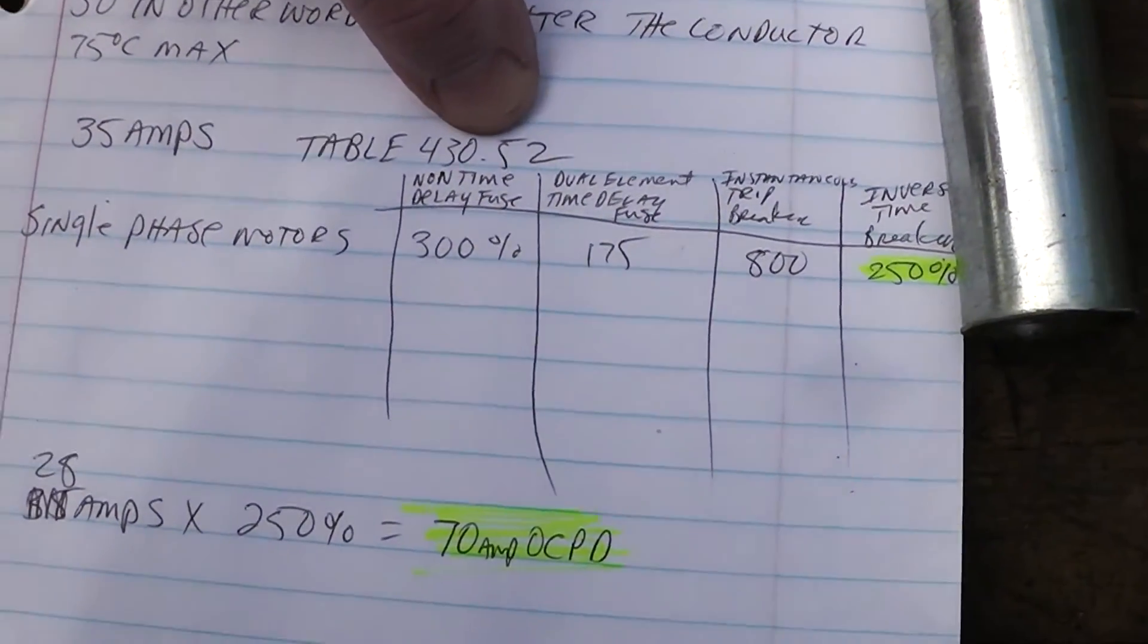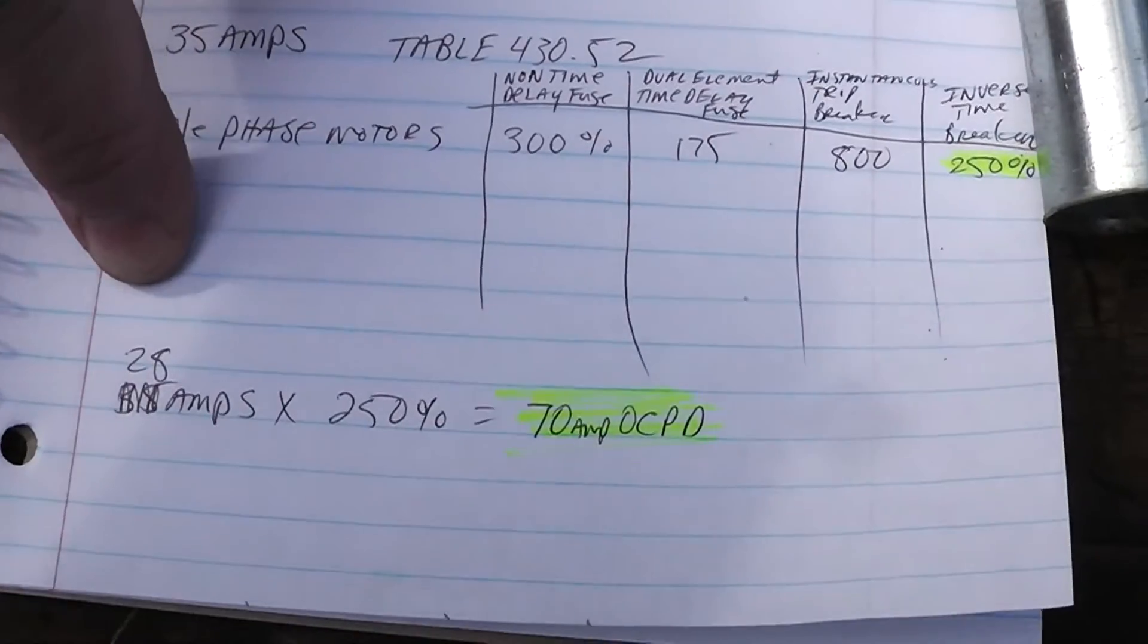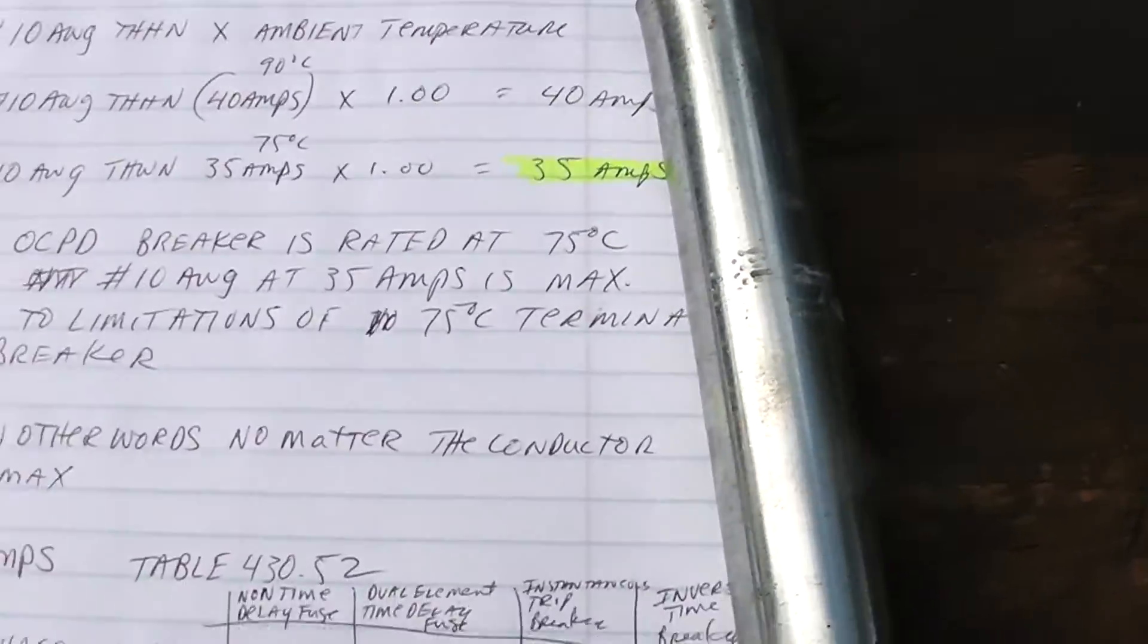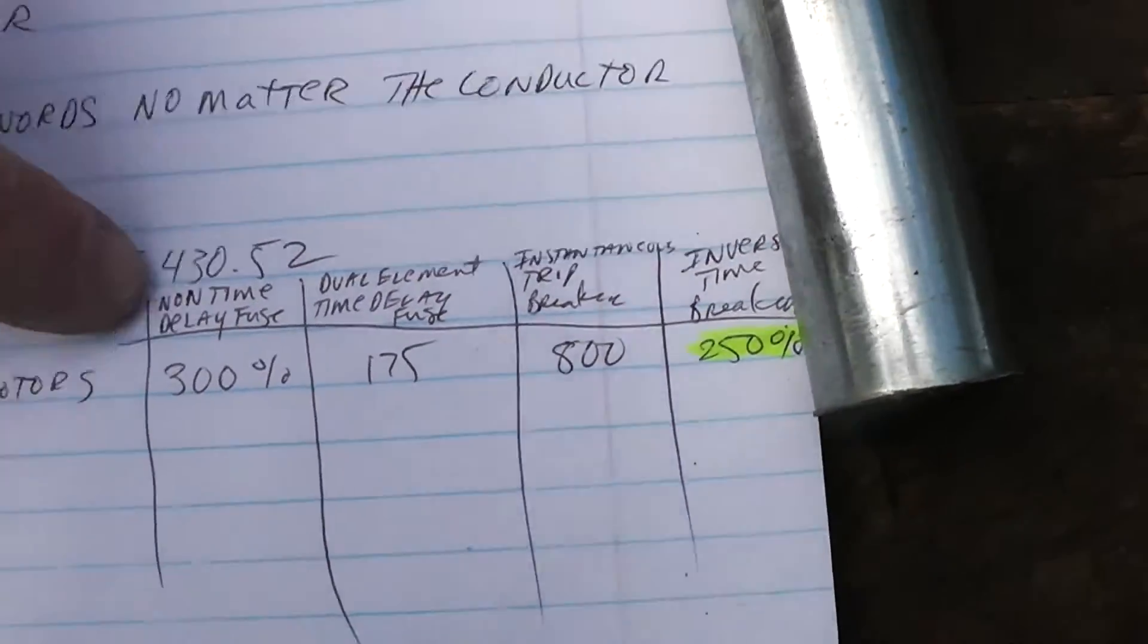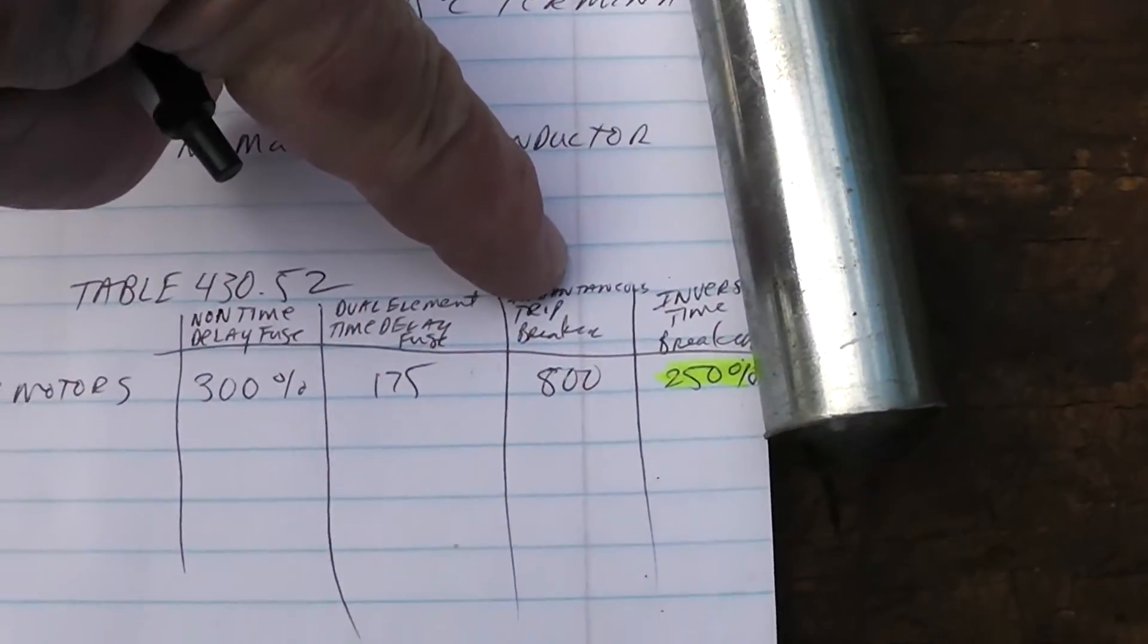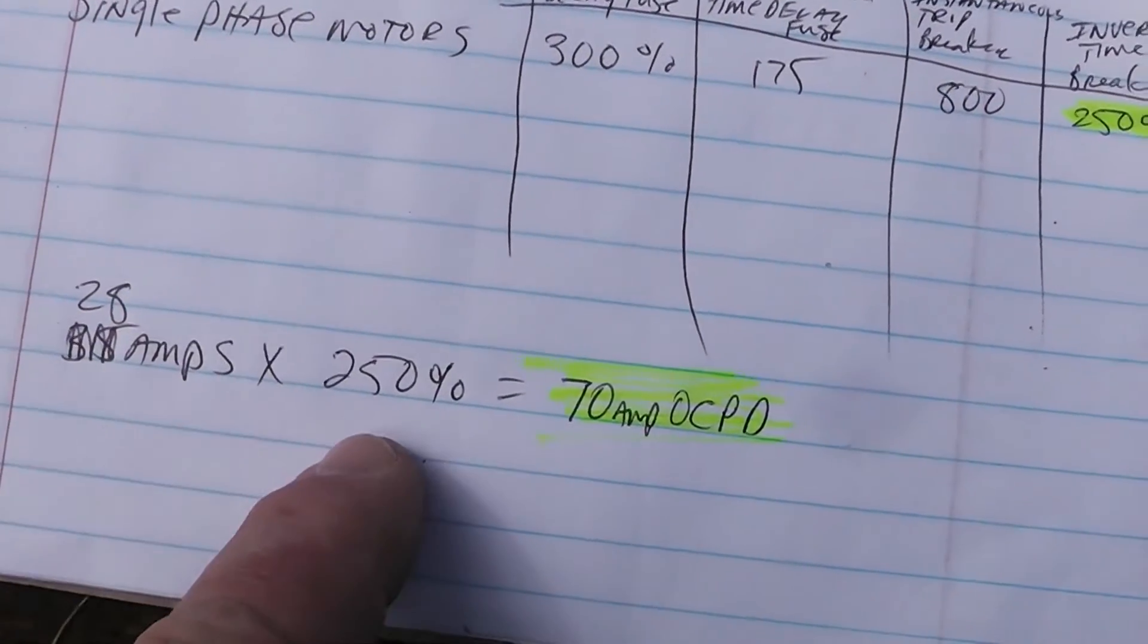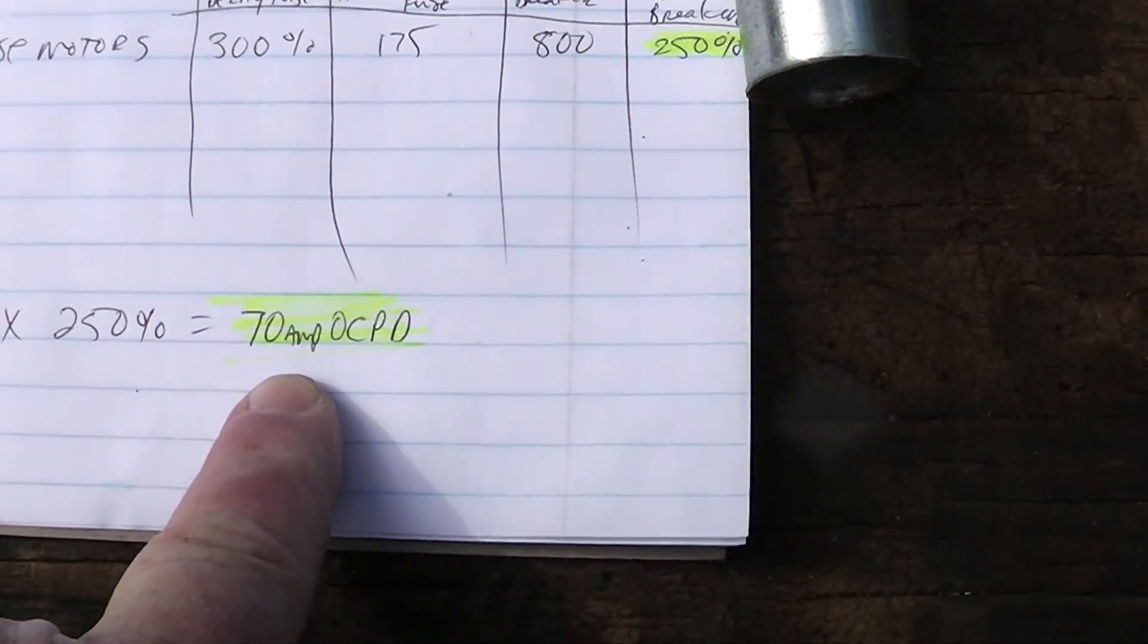Now how do we get to a 70 amp breaker? We go to table 430.52. The conductor has to be rated for 35 amps, but the full load current is what we use - that's 28 amps according to that table. We multiply that by 250 percent. If you're using a non-time delay fuse, multiply by 300 percent. Dual element fuse is 175 percent, instantaneous trip breaker multiply by 800 percent. Here we're using an inverse time breaker, so 250 percent times 28 amps comes out to 70 amps overcurrent protection device.